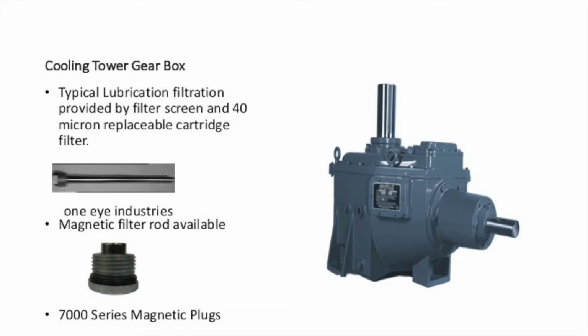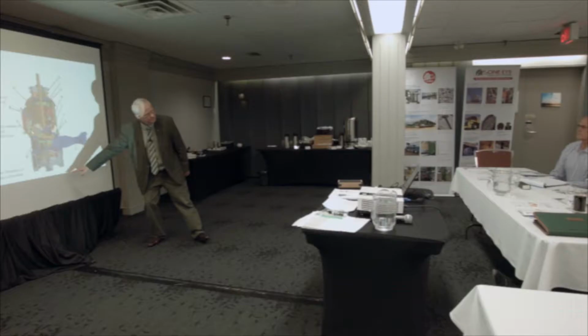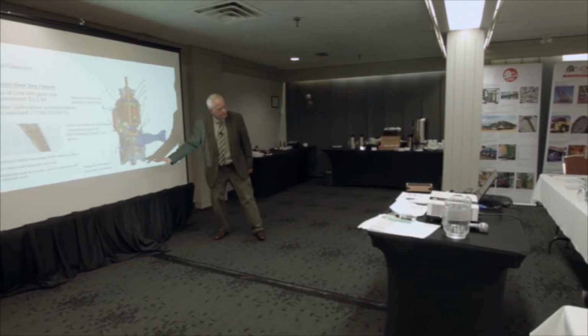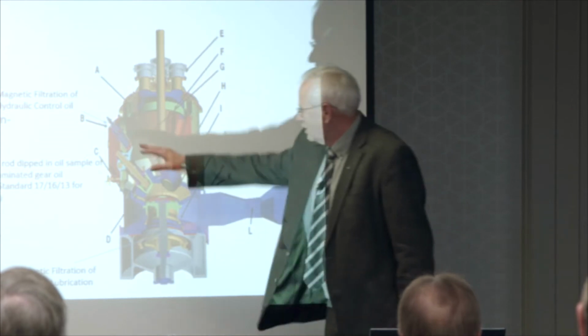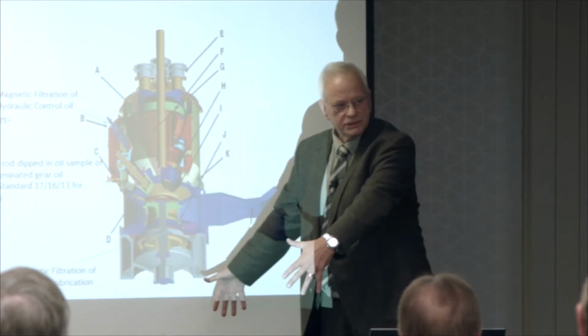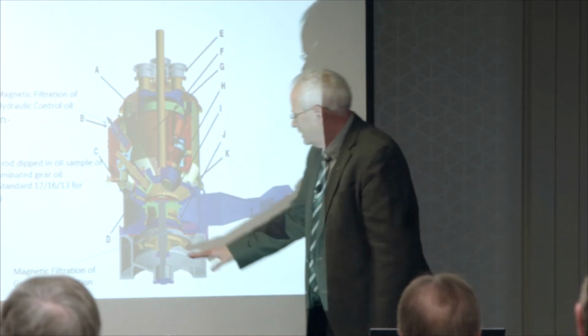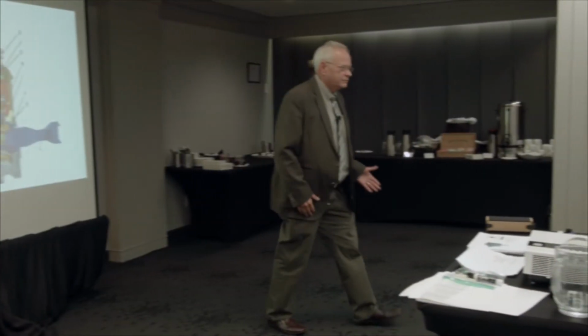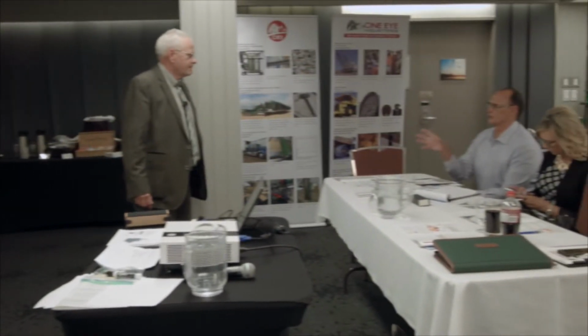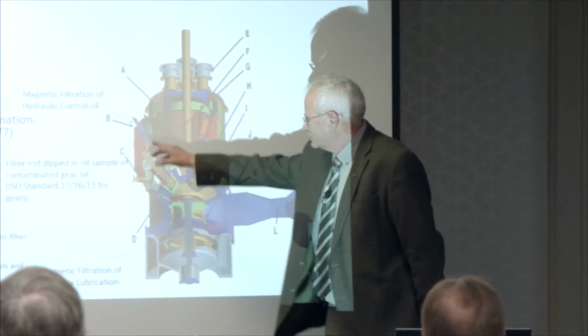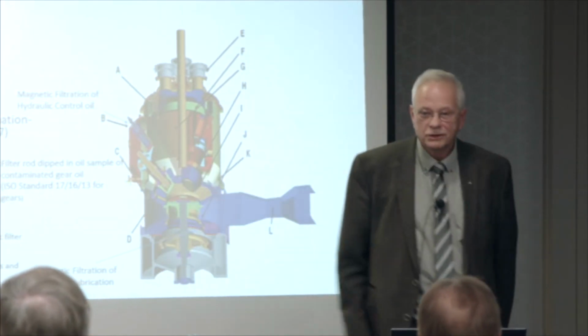So where does that 9,000 go in? Could you point out, if you don't mind, real quick? Down under the mill, our oil pumps and the filtration units were down in the sump under the mill. So you'd pipe the 9,000 right in there. That's for your gear case lubrication. For the hydraulics, they're usually at ground level, and it's just a little sump tank. You experienced the same thing with a kidney loop, right? Yeah, it wasn't effective. I'll talk to you later about it, I need to figure out where that goes. But that's where you'd put the magnetic filter, and for the hydraulic unit you'd put it on the returns to the tank.